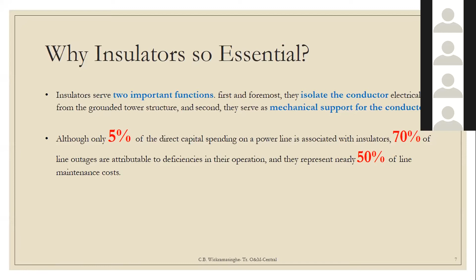We spend just 5% of the direct capital which we spend for a transmission line, just 5% of the total cost of a transmission line, towards the insulators. But 70% of line outages happen due to the failures of insulators, 70%. And also we spend 50% of maintenance costs in order to maintain the insulators, replacing or whatever. So as you can see, even though the first number is 5%, the last two numbers are very much higher.